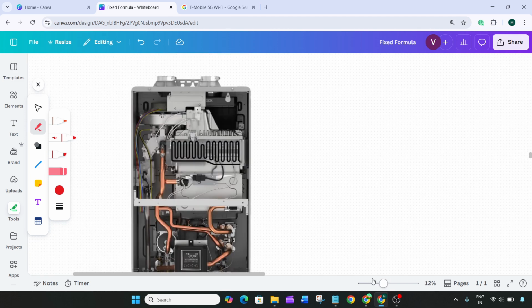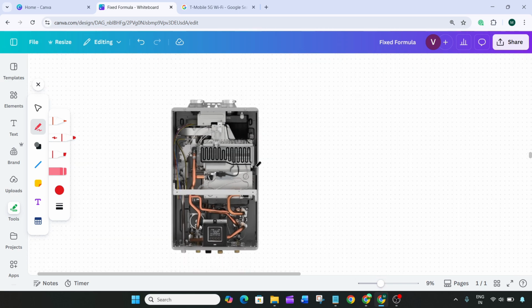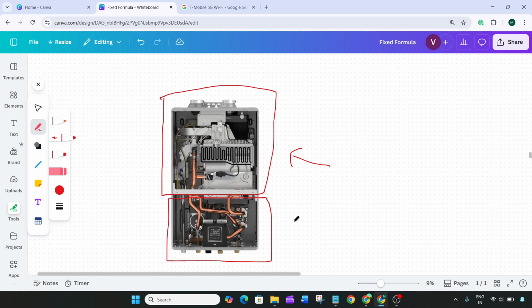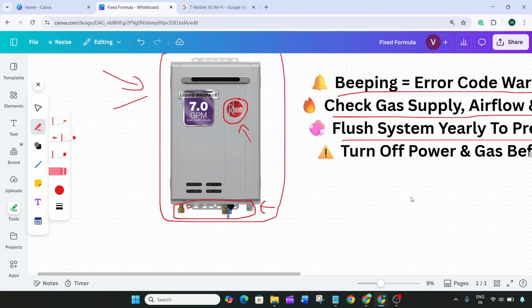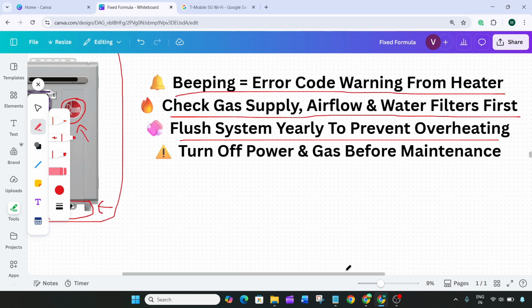To fix most beeping issues, start with simple checks like confirming the gas valve is open, ensuring vents are clear, and cleaning both air and water filters. Mineral buildup is another common cause, especially in hard water areas, so flushing the system yearly using a vinegar solution helps prevent overheating and efficiency loss. Also, inspect for leaks, corrosion, or debris buildup since these can slowly lead to bigger failures.